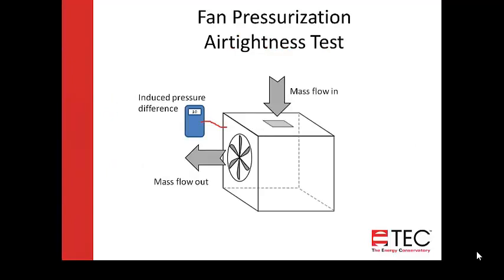We're going to start out with just the basics — a simplified version of what a blower door test is. The mass of airflow in needs to equal the mass of airflow out in a building. The basics of a blower door test is we induce a pressure — we change the pressure in the building by a given amount and then measure the airflow blowing through the fan. We know an equal mass of air leaks in, so we can figure out how tight or leaky a building is.